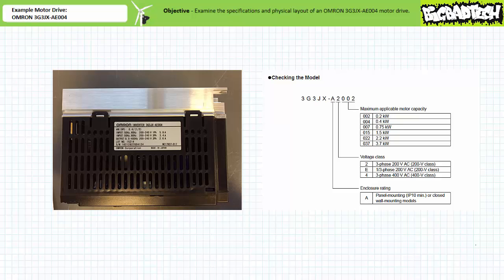The model is obviously a 3G3JX. The enclosure rating of A specifies it can be panel or closed wall mounted. The voltage class entry of E specifies this motor drive can use single or three phase AC with a nominal 200 volt input.